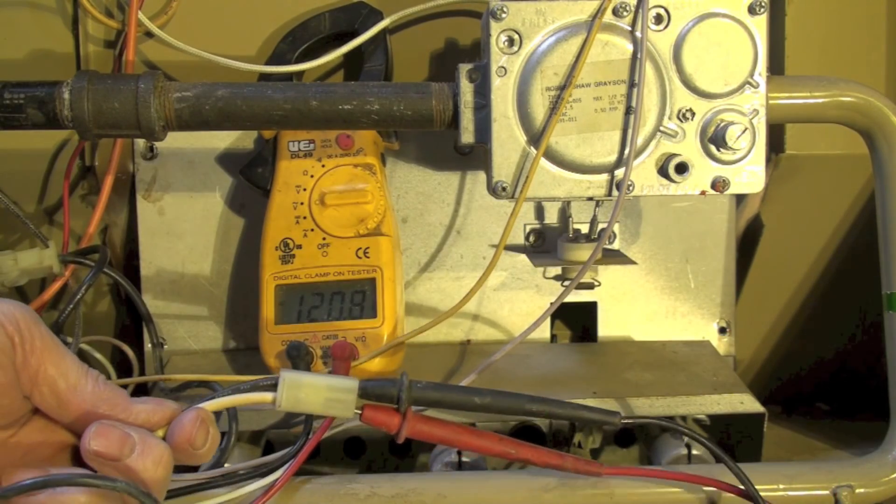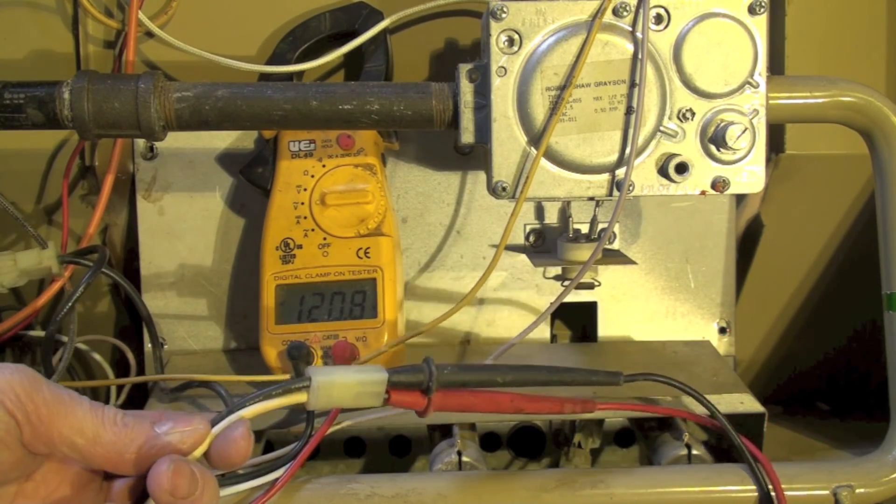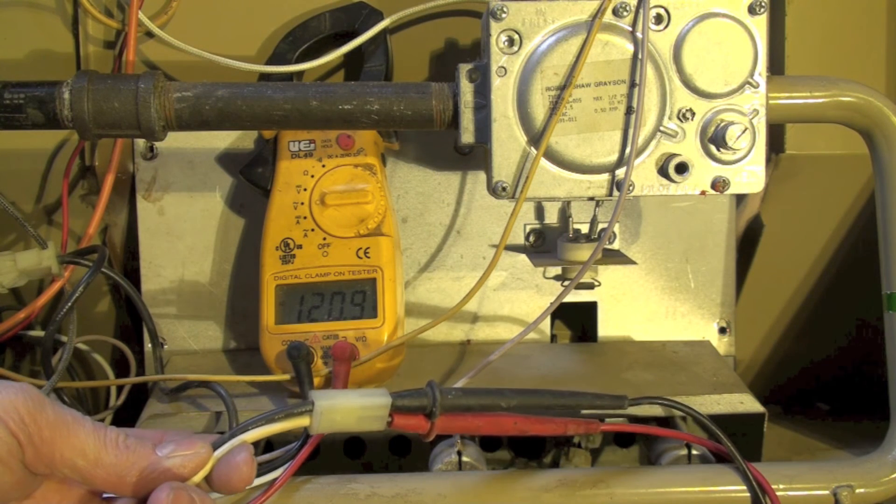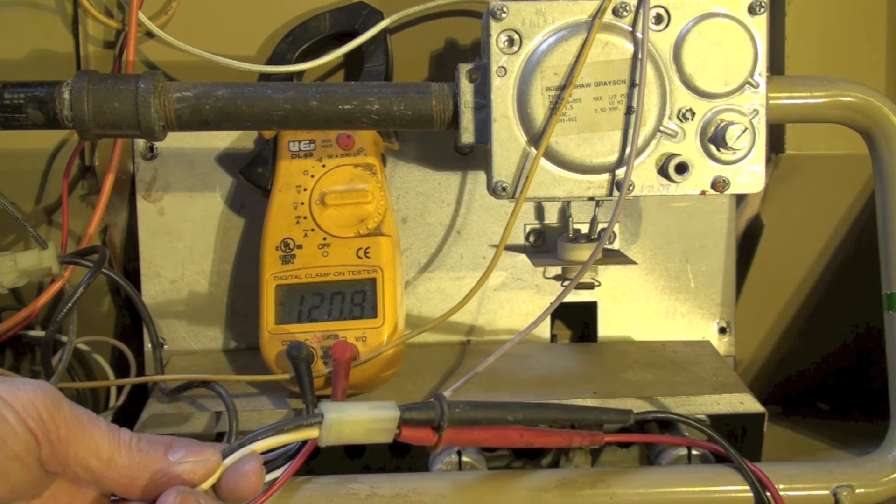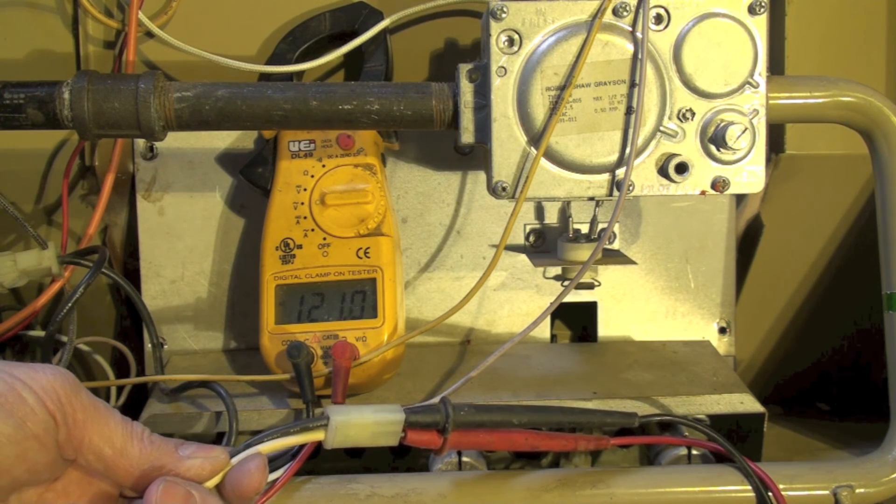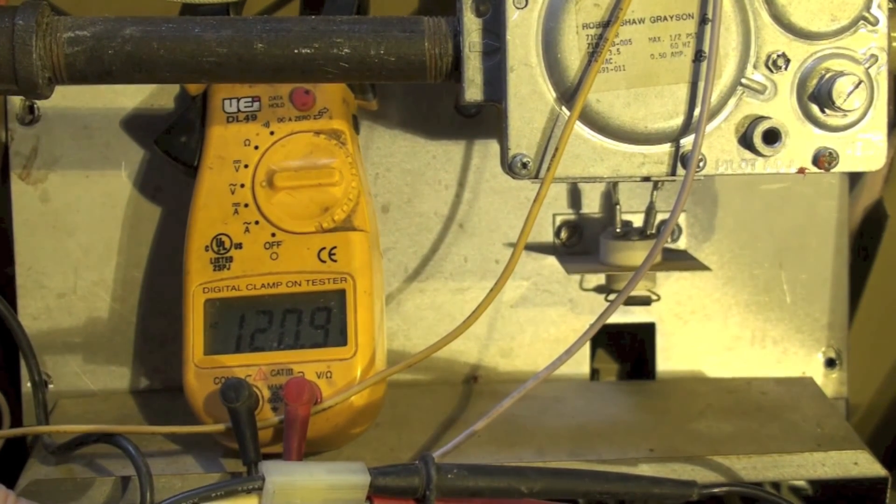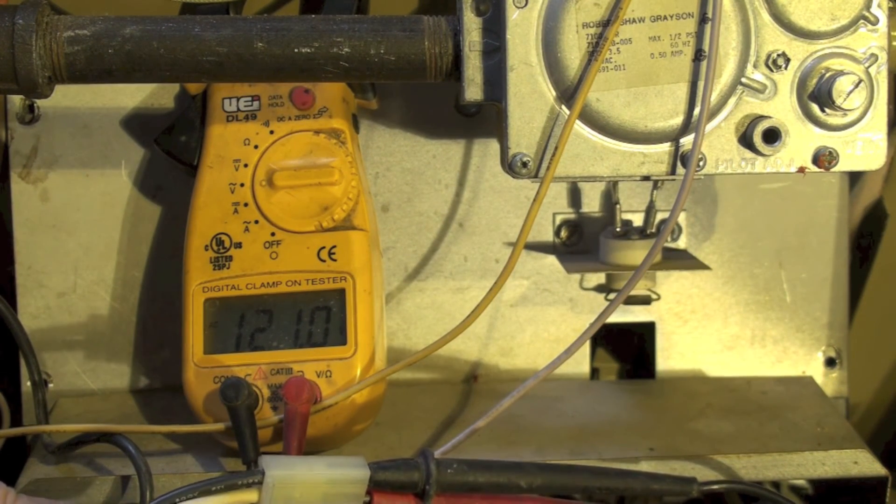Now here you can see I've set my probes onto the wire coming from the ignition control to the hot surface igniter and I'm showing 120 volts. So I got power going to the hot surface igniter, but the hot surface igniter is not coming on.